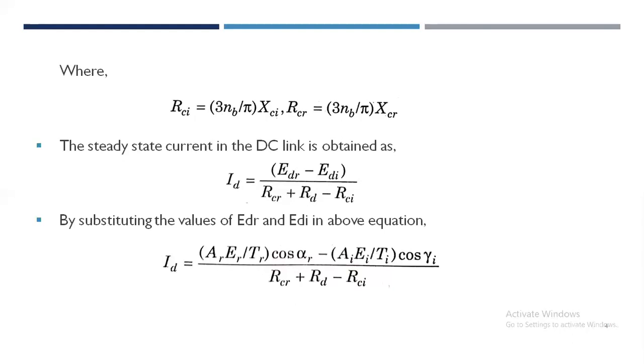The direct and fast control over the current is also desirable from the viewpoint of limiting the overcurrent in thyristor valves, which have limited short-term overload capacity. It is to be noted that although current and power can be controlled by changing the transformer taps TR and TI, this can be achieved only by slow control of mechanical switches.